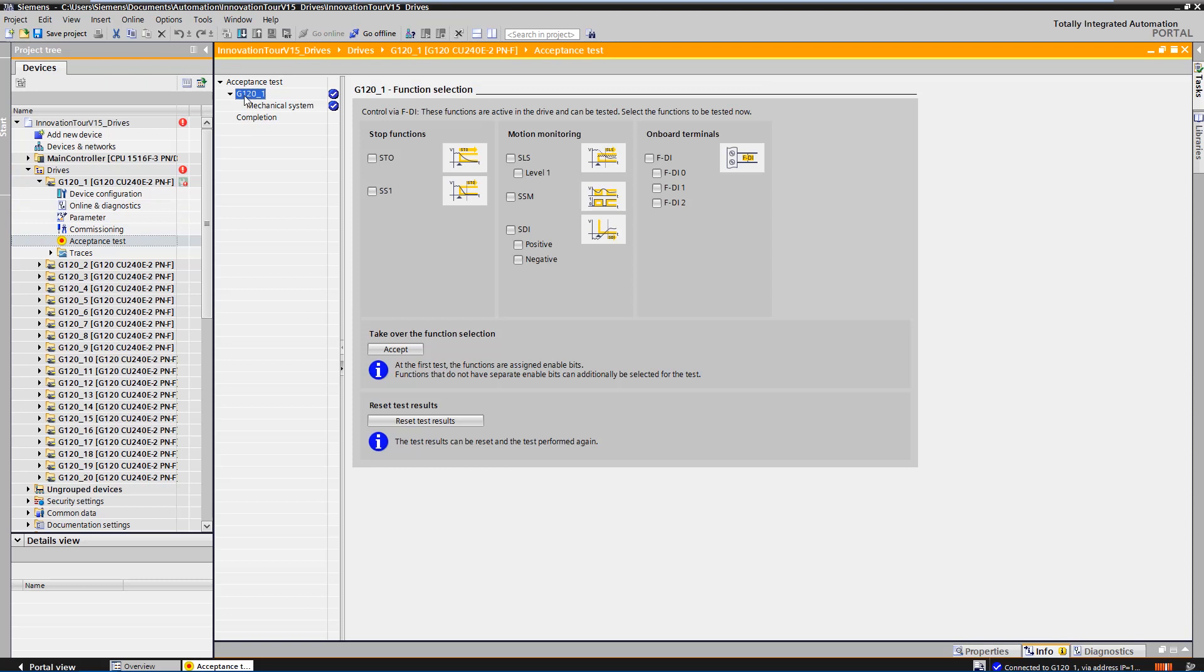Now we start with the acceptance of the safety-integrated functions. On this page, you can see which safety-integrated functions are available in the drive. Now we select the acceptance of safe torque off, safe-stop-1 and safe-limited-speed and take over the function selection.